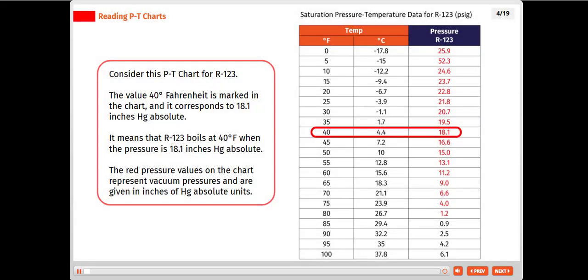Consider this PT chart for R123. The value 40 degrees Fahrenheit is marked in the chart, and it corresponds to 18.1 inches mercury absolute. It means that R123 boils at 40 degrees Fahrenheit when the pressure is 18.1 inches of mercury absolute. The red pressure values on the chart represent vacuum pressures and are given in inches of mercury absolute units.